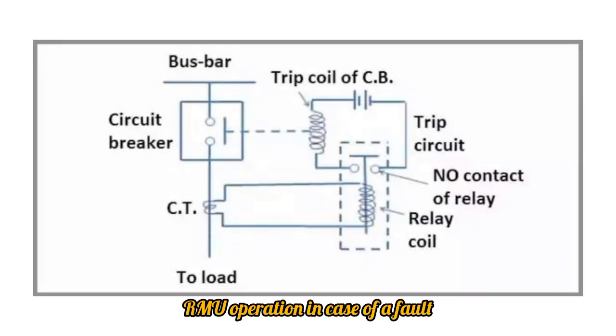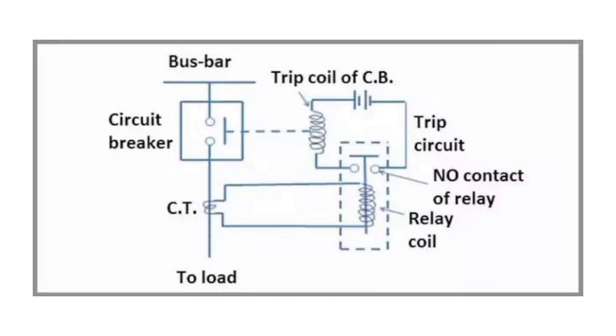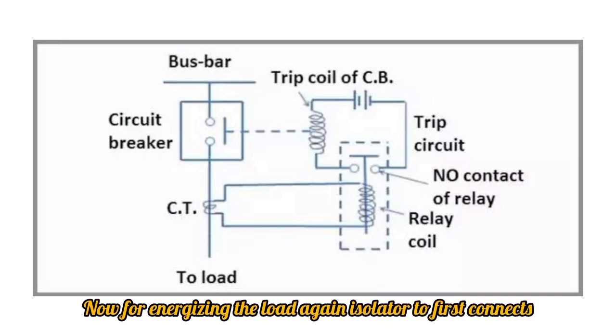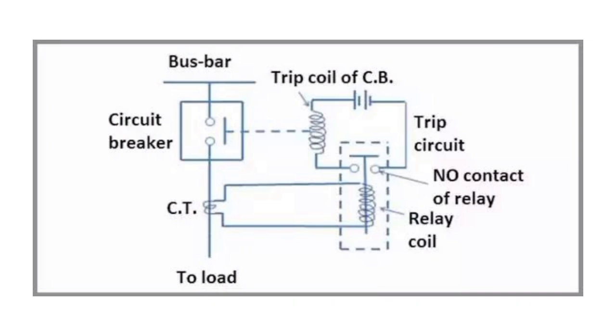RMU operation in case of a fault. For example, if a fault occurs at the feeder one side, then first of all the relay will issue a trip signal to the load side circuit breaker to open first, and then both isolators disconnect. Now for energizing the load, again isolator two first connects and then the breaker is closed.